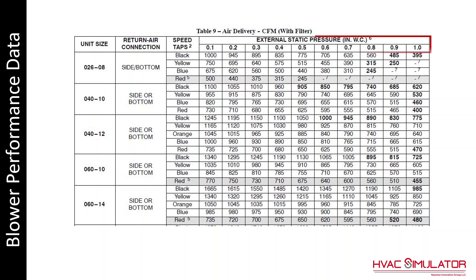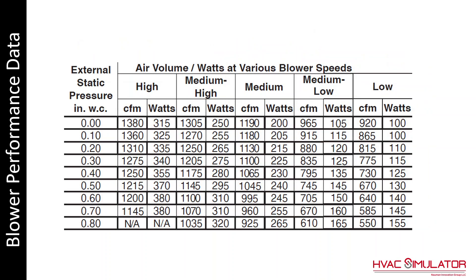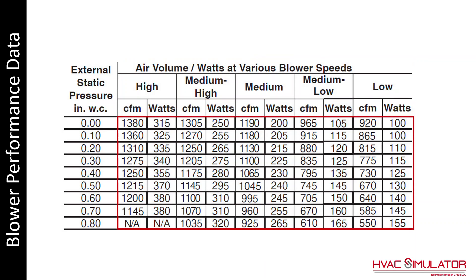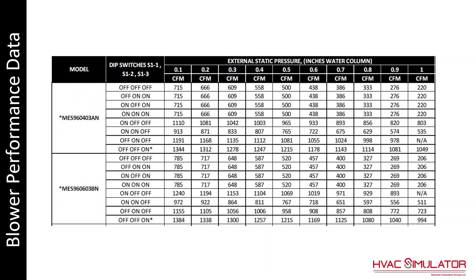External static pressure is shown on the top of this chart, and the blower speed taps are on the left, with the CFM values in the body. On another chart, the external static pressures are listed on the left column and the blower speeds on the top row, with CFM values in the body. Another manufacturer has external static pressure on top but uses dip switches to set the CFM, with CFM values in the body.